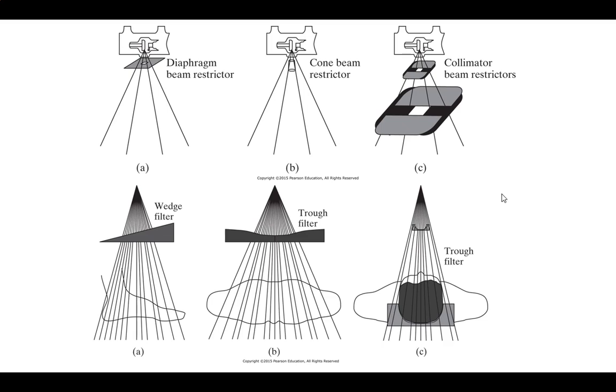So generally, I want to get an even exposure all the way through. And again, remember, even exposure isn't just so that it looks pretty and even for the doctor. Remember, the range of energies coming in versus those coming out tells you your ability to get contrast. So if you've got too much coming in the toe region, it's going to be a washed out image. It's not just that it's going to be a different intensity. The range is not well preserved, so it's going to saturate, and you're not going to be able to get a good distinction.